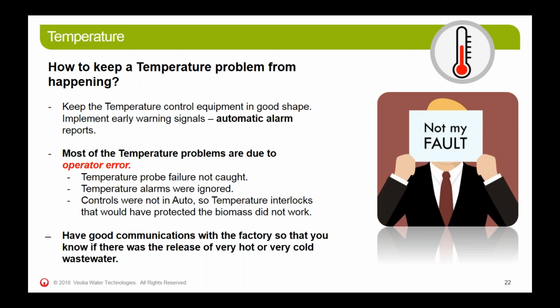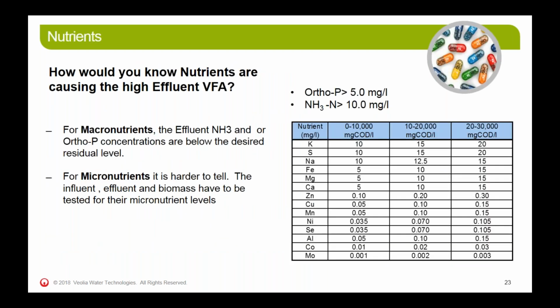Again, if you have the system in auto, you can set your alarms and interlocks appropriately so that the system would shut down before the bacteria were damaged. Again, good communications with the factory are really helpful to help ease these problems. Next.